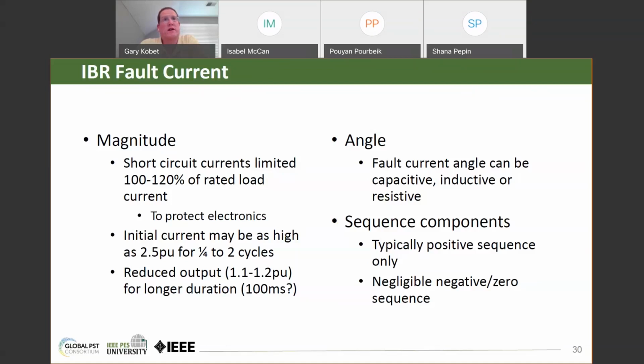The other thing about synchronous machine currents is that they become significantly higher, 5 or 6 times maybe what the load current is. But for IBR, most of the time the short circuit currents are limited to about maybe up to 120%. You may get an initial increase in current up to 2.5 per unit, but only for a quarter to 2 cycles. But the IBR devices are protecting themselves from overcurrent, and so they reduce that current output.